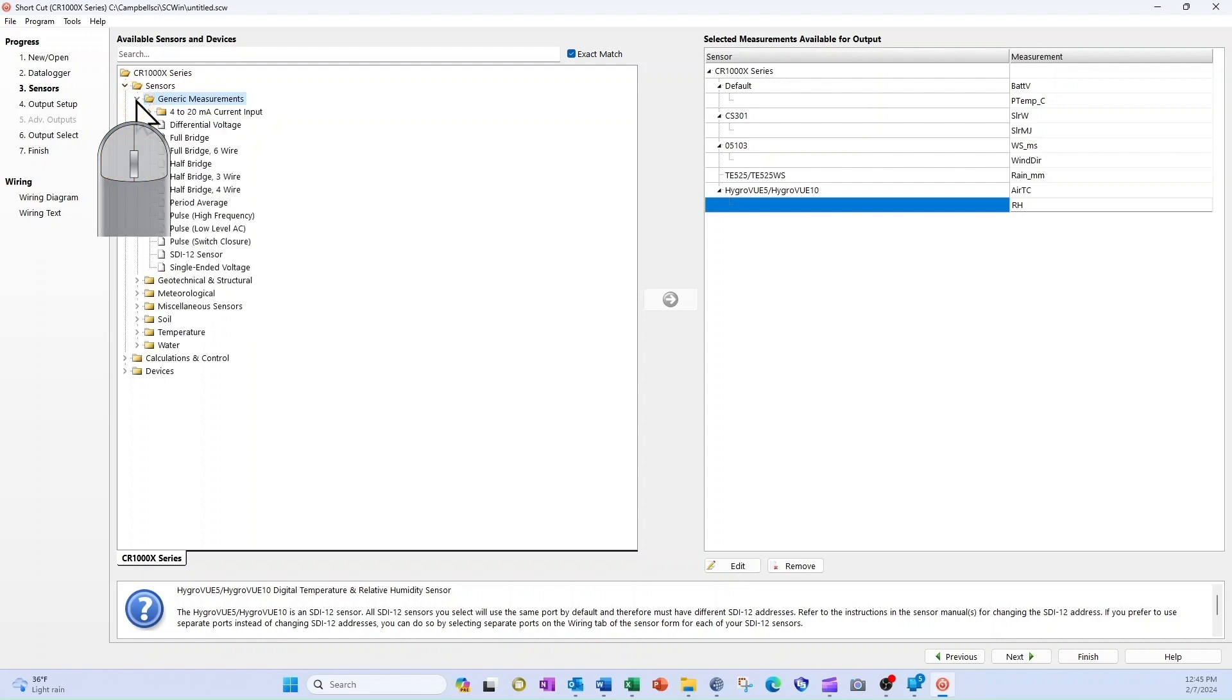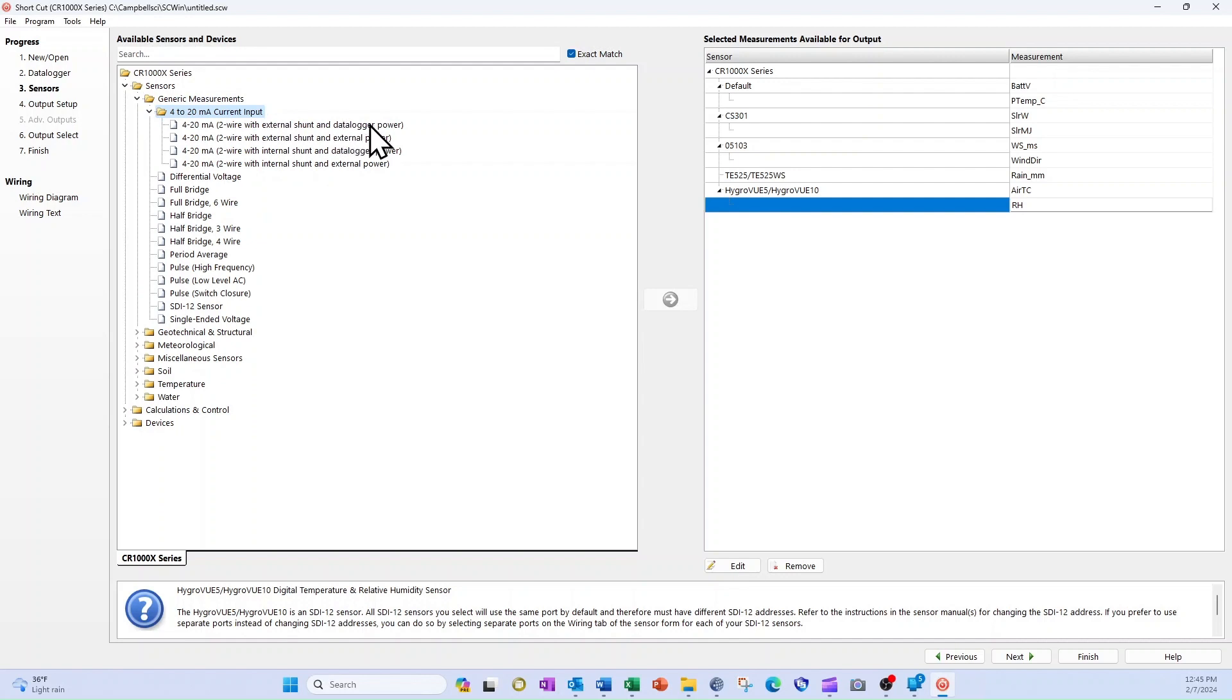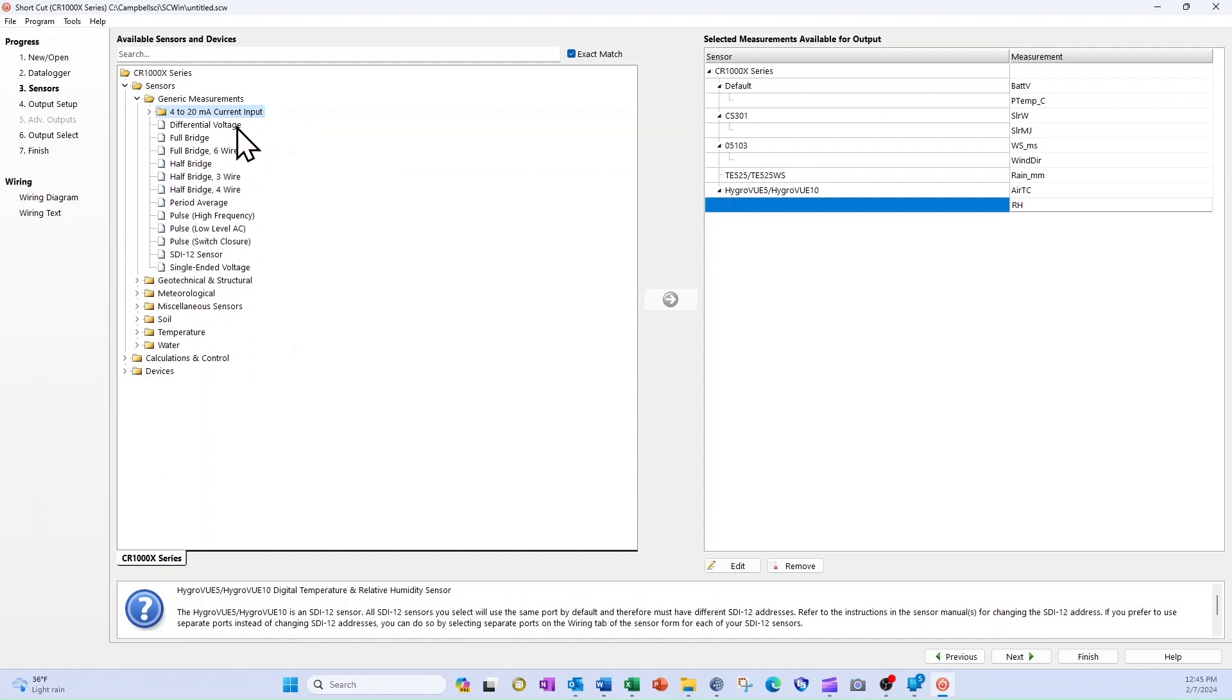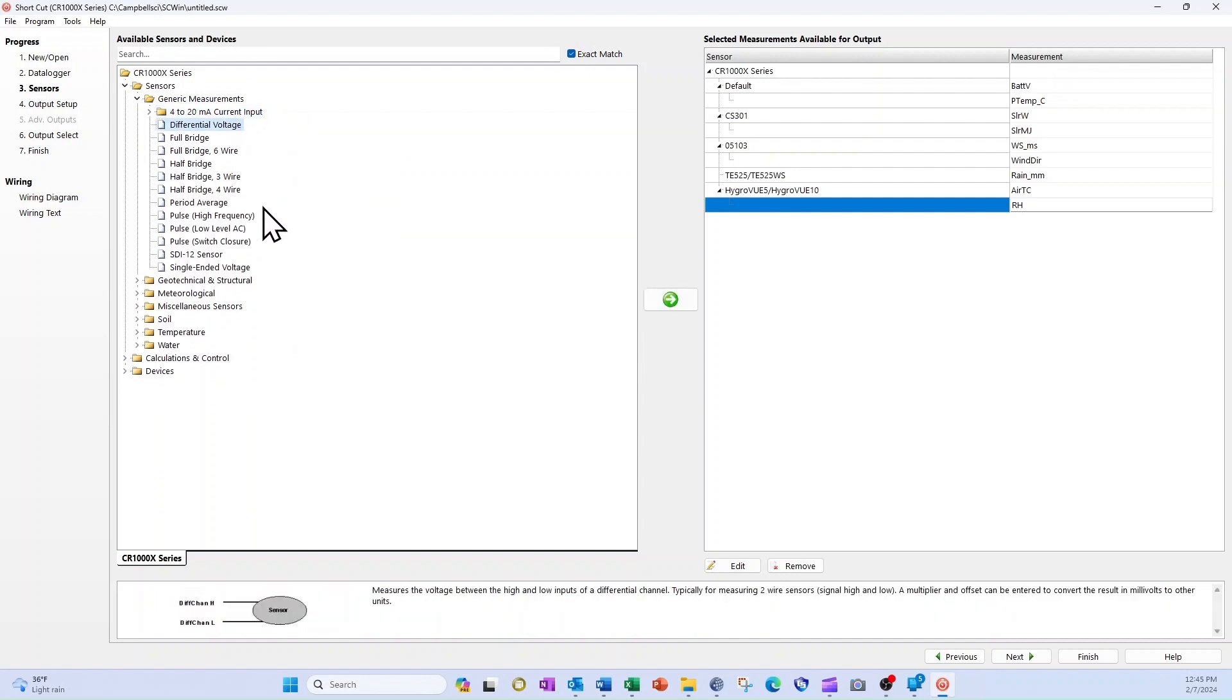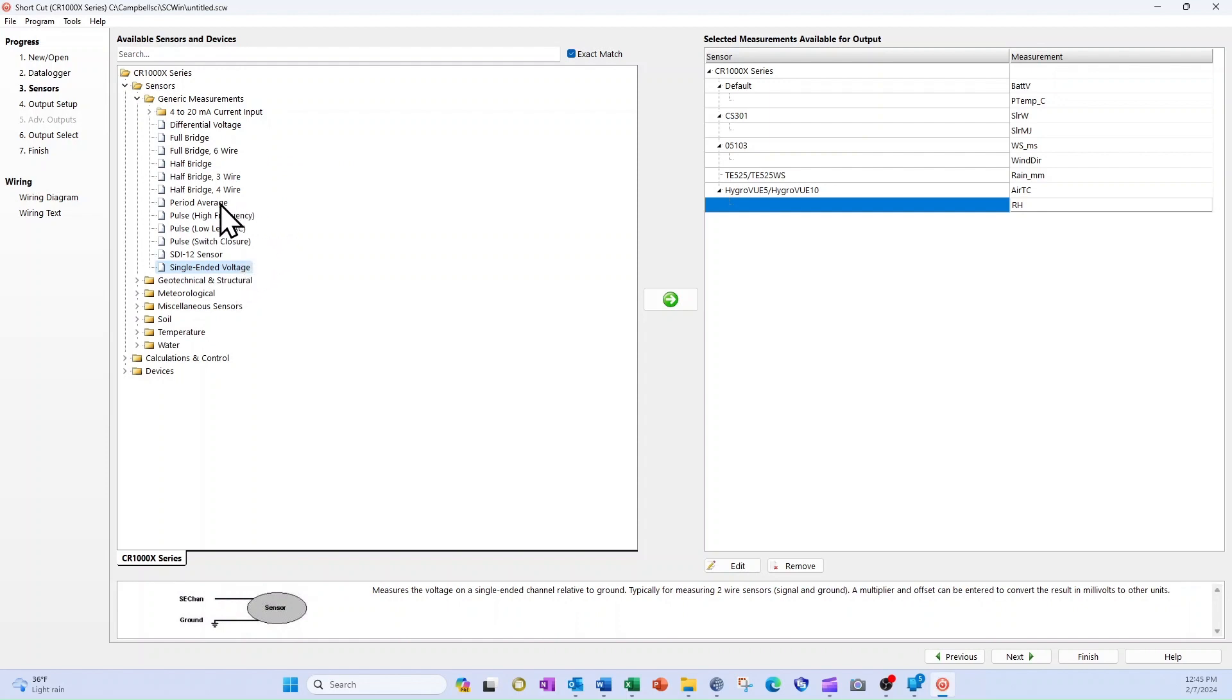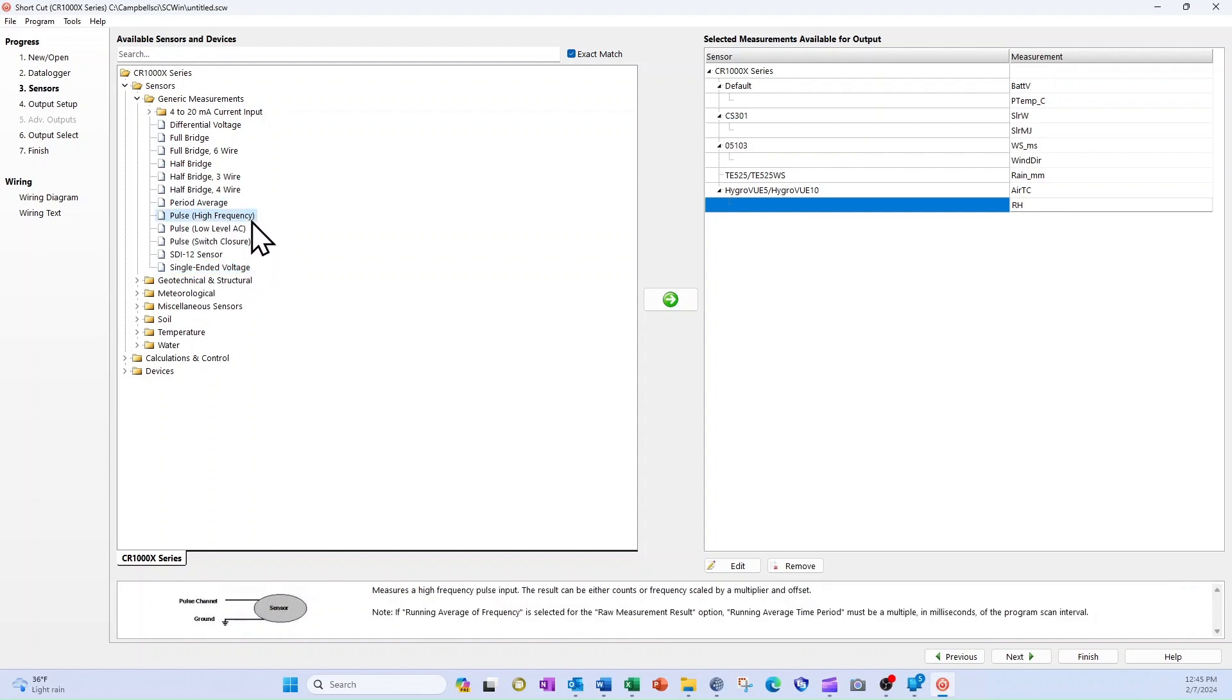If my sensor output is 4 to 20 milliamps, I will select one of the options in the 4 to 20 milliamp current input folder. If the output is a steady voltage, I select differential voltage or single-ended voltage. For variable voltage signals, I can select period average or a pulse measurement.